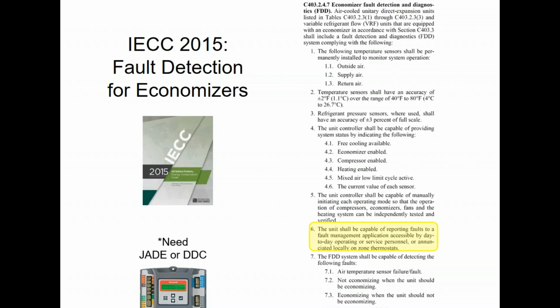That's basically your building automation system, accessible by day-to-day operating or service personnel. So it can't just be on the screen, in this case the Jade controller in the corner, up inside the rooftop. That's not accessible to day-to-day people. It's got to be pushed back down to your building automation system where it can be displayed on the computer monitor, or emailed to the building guy, or texted to the service provider or something like that.